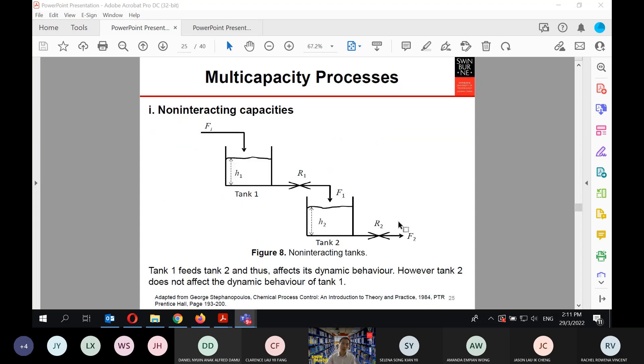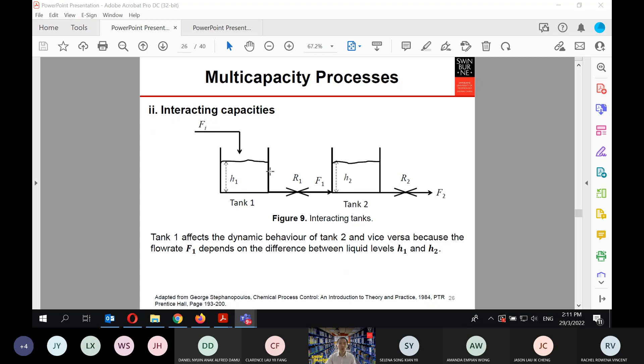For non-interacting capacities, the outlet from the first tank feeds into the second tank. Tank one affects tank two's dynamic behavior, but tank two does not affect tank one. For interacting capacities, both tanks are at equal level so the flow rate F1 depends on the difference between liquid levels h1 and h2 — they interact with each other.